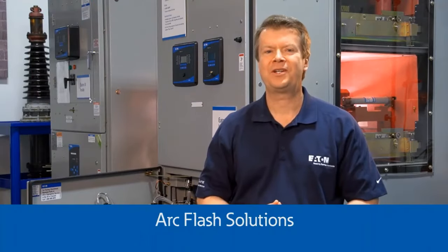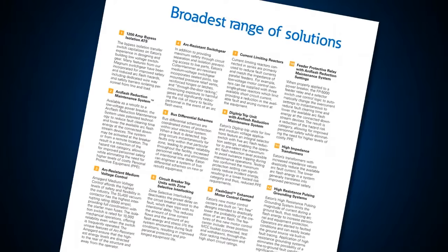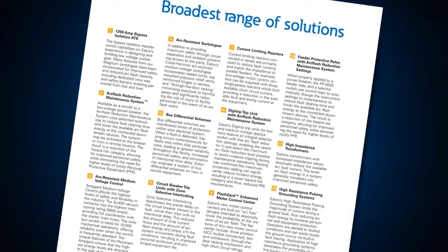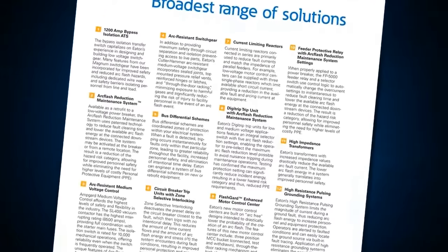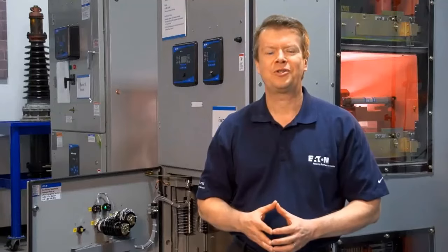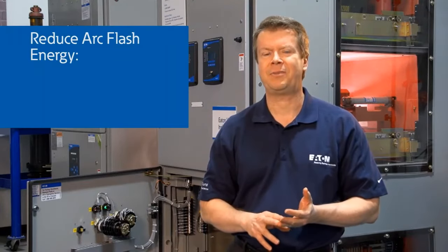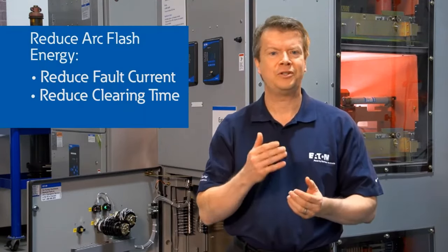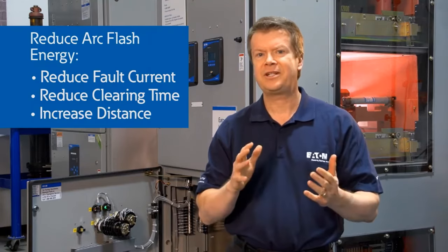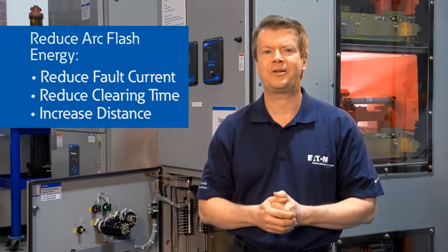Eaton has nearly 100 solutions for arc flash safety. And here at the Power Systems Experience Center, we can introduce you to all of them. We focus on opportunities to reduce the arc flash energy by reducing the fault current, reducing the clearing time, and increasing the distance from the arcing fault to personnel.